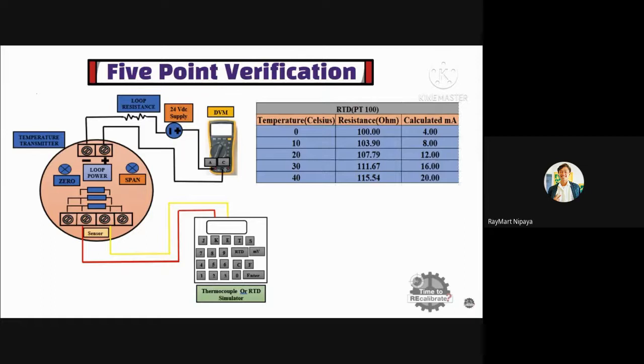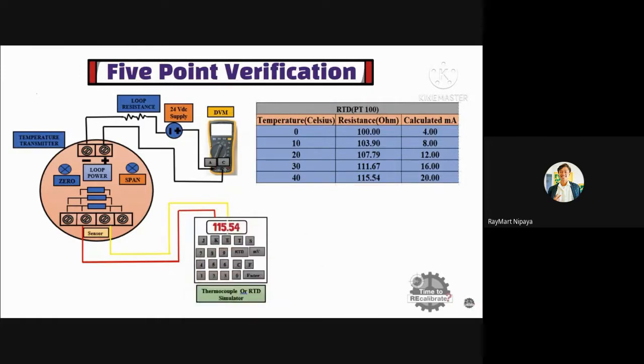Now, set 111.67 ohm resistance value in the simulator, and feed this value to the transmitter. The DVM should give a 16 milliamperes value. Finally, set 115.54 ohm resistance value in the simulator, and feed this value to the transmitter. The DVM should give a 20 milliamperes value. Once you are done with verification, disconnect the simulator from the transmitter, and also disconnect the DVM from the transmitter.